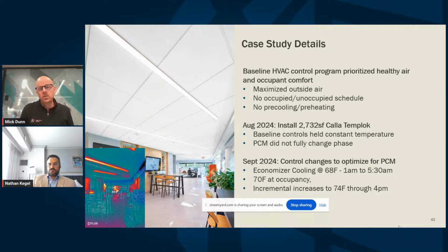And what would happen if we were to really leverage the controls and institute some of what we were talking about earlier with economizer cooling in this place? So specifically, we ran a series of experiments really focused on the cooling side of the equation, of what might happen if we intentionally cool the building down with economizer cooling, and perhaps do that for longer than we might normally do. We left the building in economizer cooling from 1 a.m. to 5:30 a.m. We wanted to guarantee that the ceiling was, no question, 100% ready for the day ahead. And typically we had a 70-degree set point at occupancy. And the strategy was to incrementally raise the set point as we neared closer to the afternoon hours.